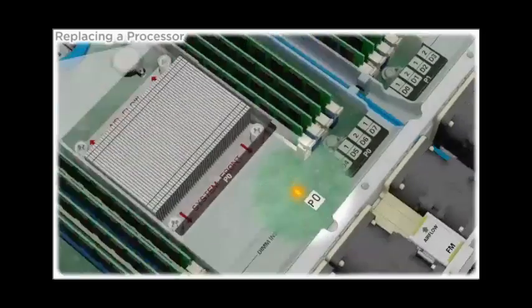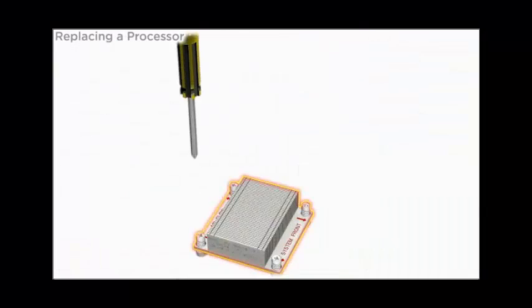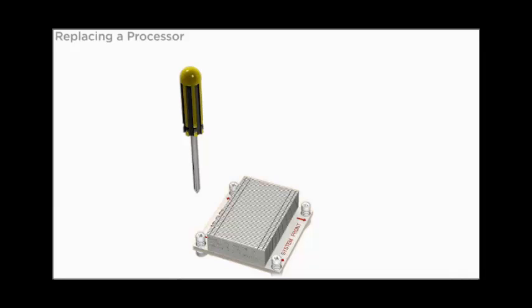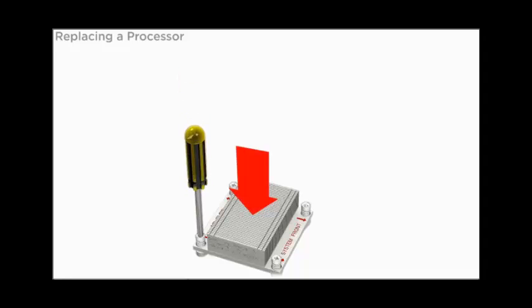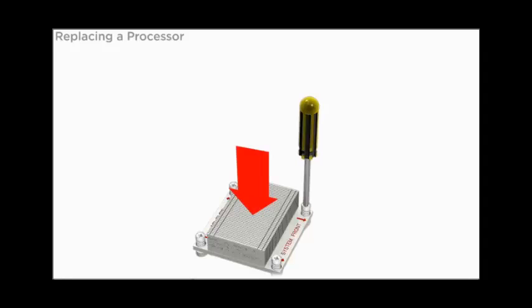To replace the processor, first remove the heat sink. Gently apply pressure to the top of the heat sink while loosening each retaining screw one and a half turns at a time.